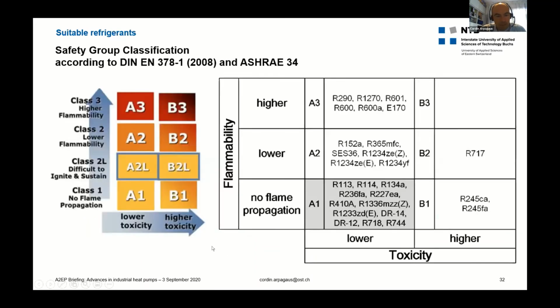This graph shows the safety group classifications according to European norms or American ASHRAE standards. It shows flammability as a function of toxicity, and ideally, the refrigerant should be in this lower corner, A1, which means no flame propagation and low toxicity.